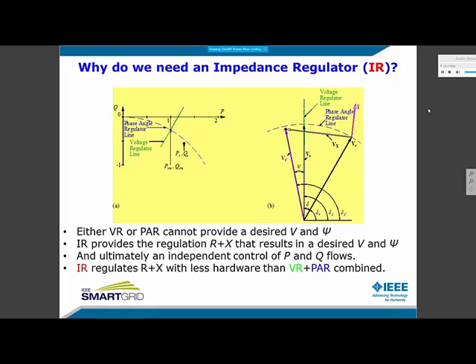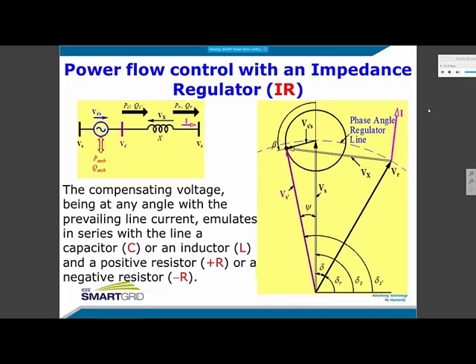Impedance regulator is the one that provides the regulation of two parameters, resistance and reactance, that results in an independent control of P and Q flows, which is shown in the next slide. Besides, the impedance regulator regulates two parameters with less hardware than the voltage regulator and phase angle regulator combined.